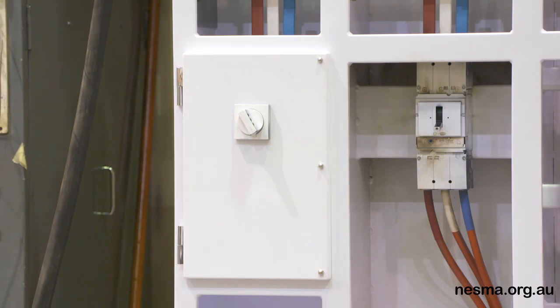This time we didn't get to see as much of the arcing because, like we did in the centre section, the cover was in place. It's held on by 3 dome nuts on the right side and 2 pintle hinges on the left side. So effectively, the unit under test was pressurised by the arc products coming out of the circuit breaker arc vents, and also a little bit of pressure that's formed by the fuse wire rupturing, and that's causing arcing on the load side terminals. What happens, of course, as soon as the arcing starts on the load side terminals, the circuit breaker is recognising the fault, operates, and then it turns the supply off to those load side terminals, and then everything being well and good, the equipment is just in a position with that final circuit disengaged.